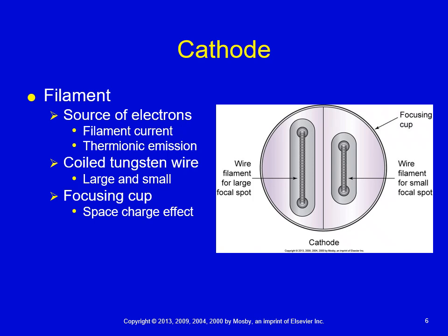press the prep switch, this is something that you probably learn in procedures. You're applying what we consider a current or an amperage to the filament. As we apply that amperage, the filaments get very hot to the point of incandescence. And as it gets hotter, it boils off those electrons that we need for the patient's X-rays.